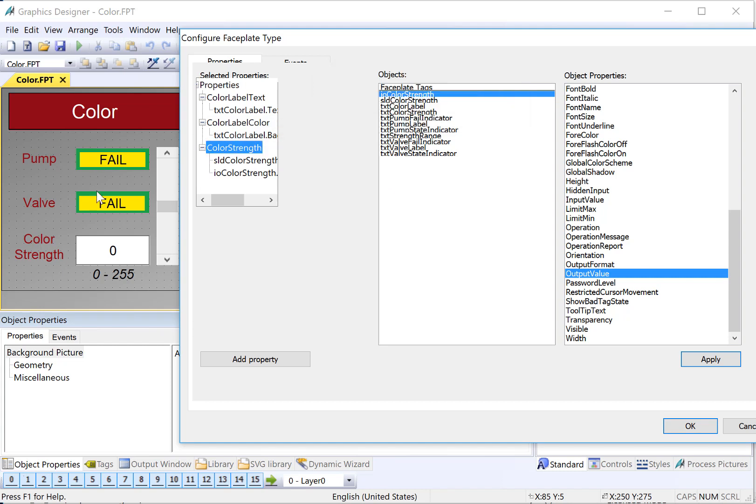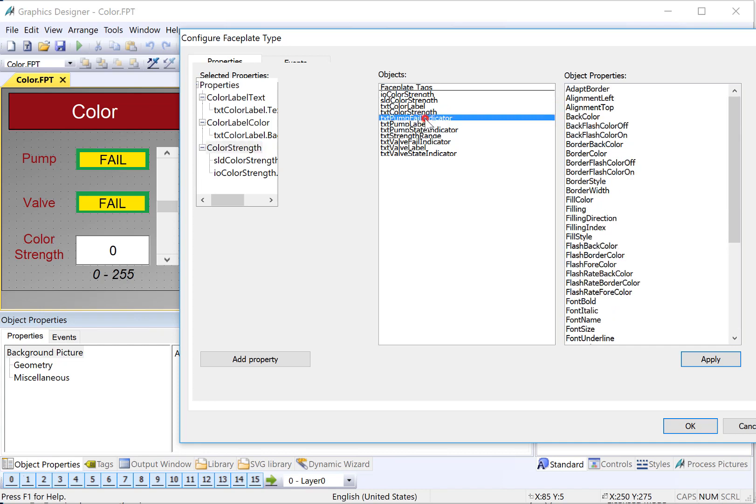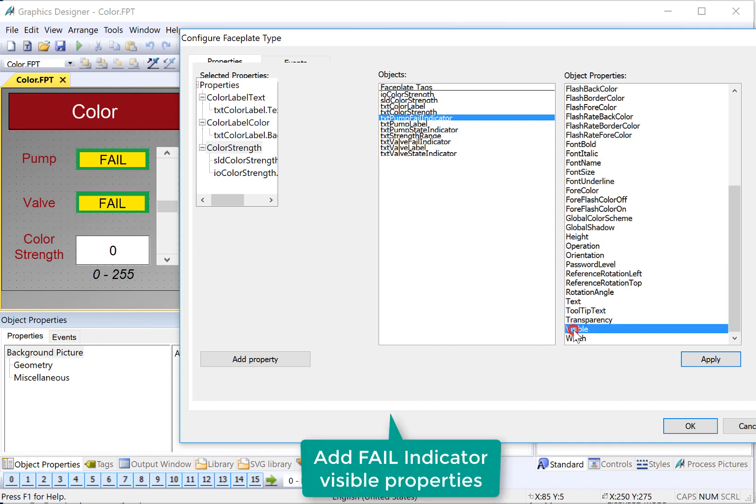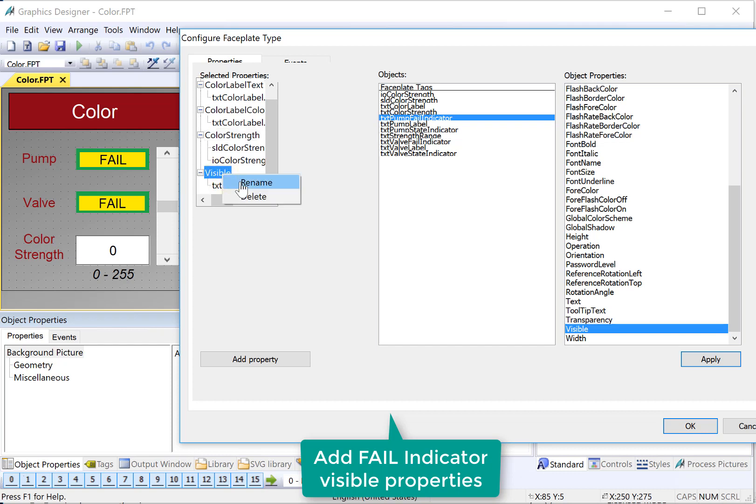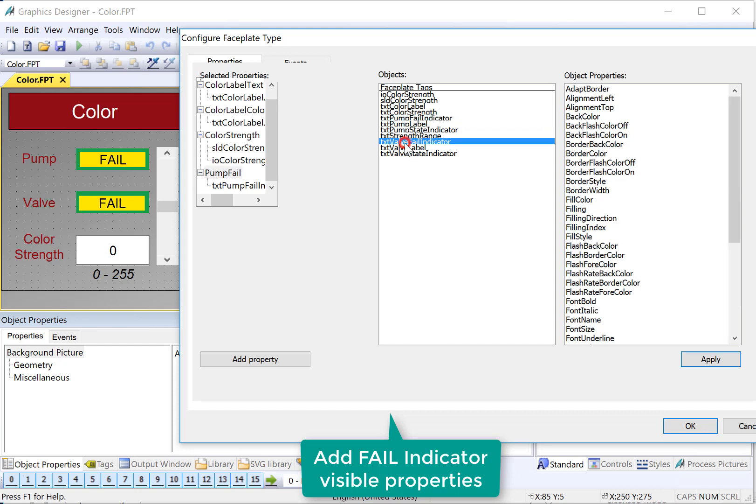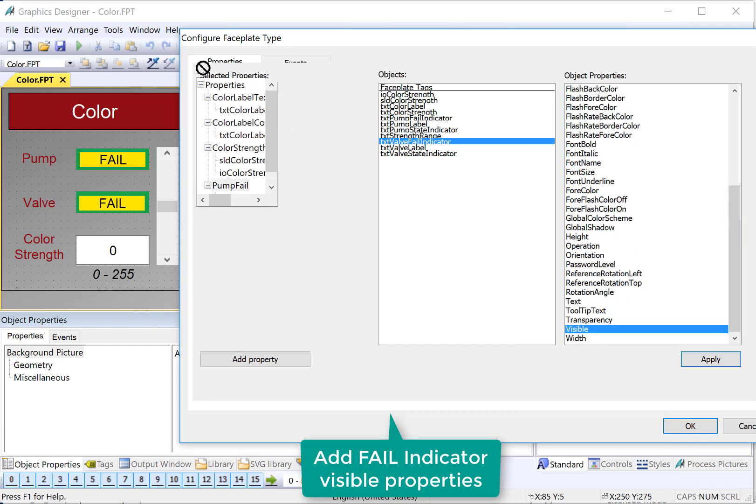We also want to do our fail indications for pump fail and valve fail. And so for these indications, we're going to turn off the visibility if the failure mode is not active. So we will find our pump fail indicator, which is this yellow box here. And we're just going to grab the visible property, drop it there, rename it, call it pump fail. And we will do the same thing to our valve fail indicator, visible, put it under properties.